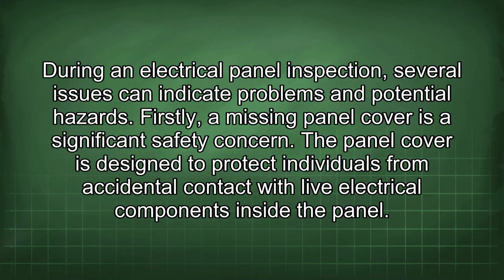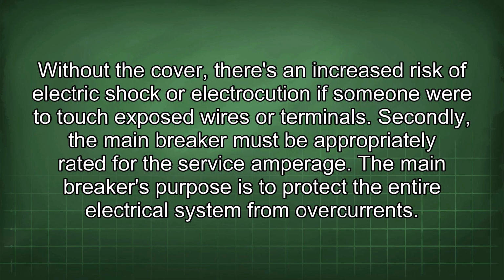During an electrical panel inspection, several issues can indicate problems and potential hazards. Firstly, a missing panel cover is a significant safety concern. The panel cover is designed to protect individuals from accidental contact with live electrical components inside the panel. Without the cover, there's an increased risk of electric shock or electrocution if someone were to touch exposed wires or terminals.